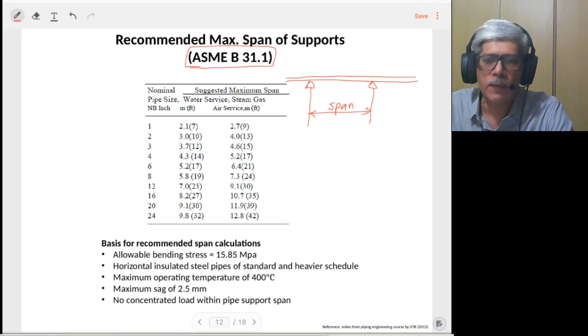The piping code itself provides what should be the recommended span of the support. So if you have a long pipeline and you are providing supports, what is the maximum span between any two supports recommended by the code? If you look at the ASME B31.1, which is the power piping code, it gives you the maximum span of the supports. Depending on the pipe size, the spans are defined and they are given for different services.